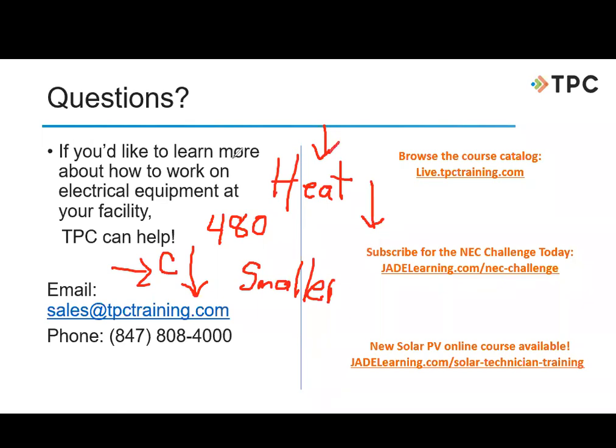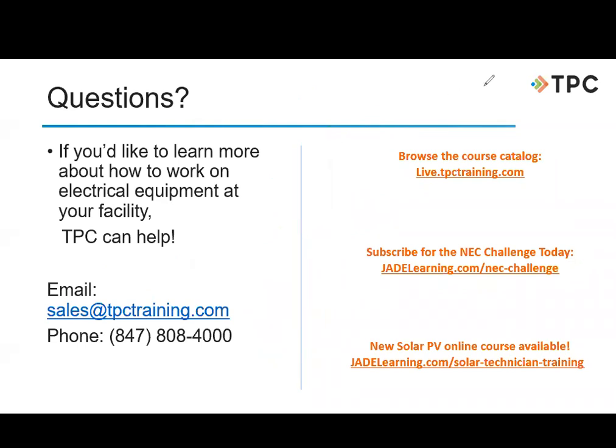As far as the cost of paying the utility, it's not going to be a big difference between 208 or 480. But overall, it is going to be much better for us in the long run because it's going to be better on our equipment. It's going to make our equipment last longer. Our conductor sizes can be smaller, and the 480 is definitely going to allow us to sustain our equipment for a much longer period of time.